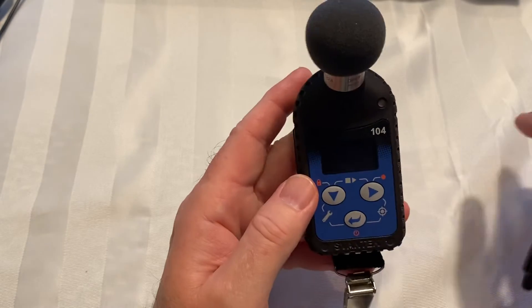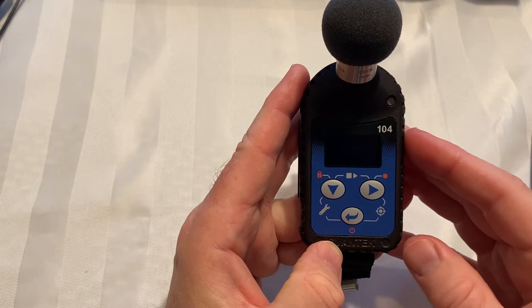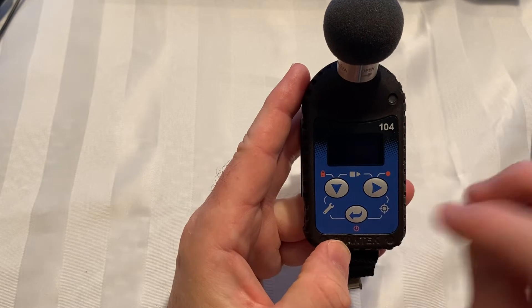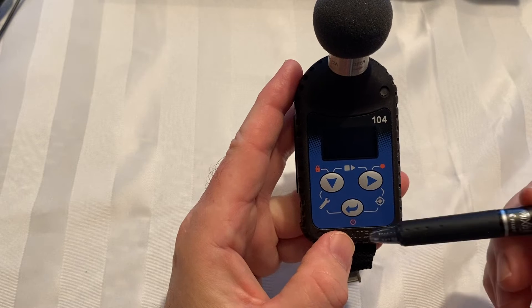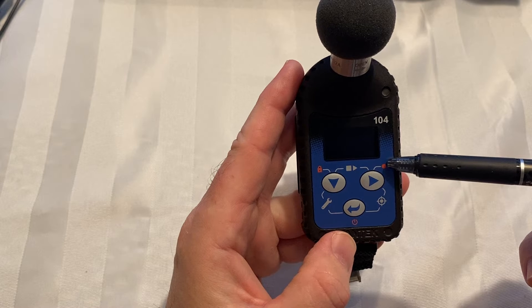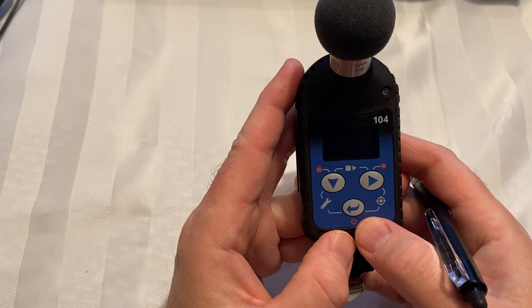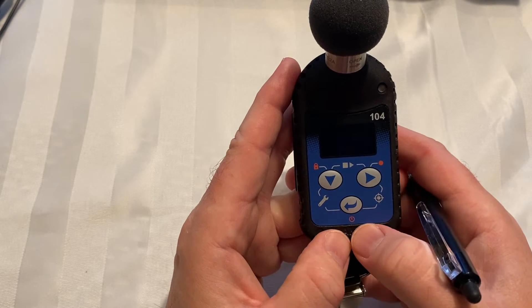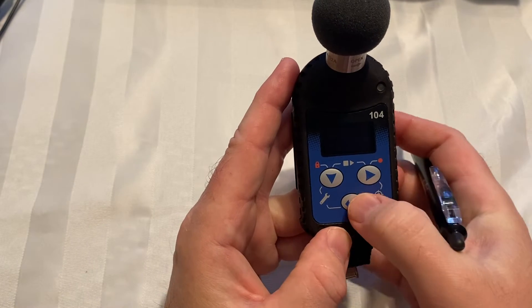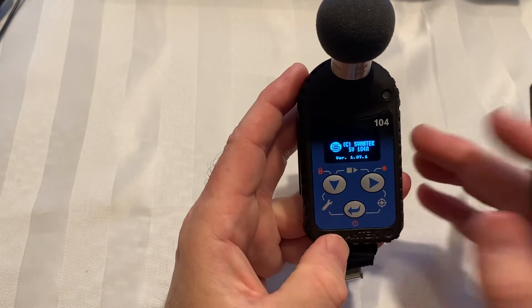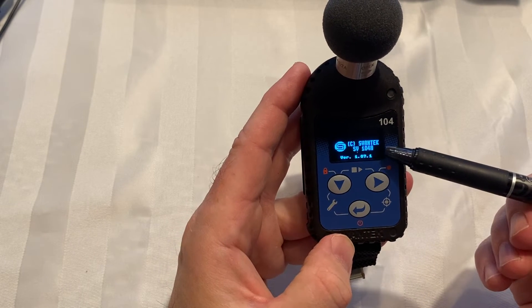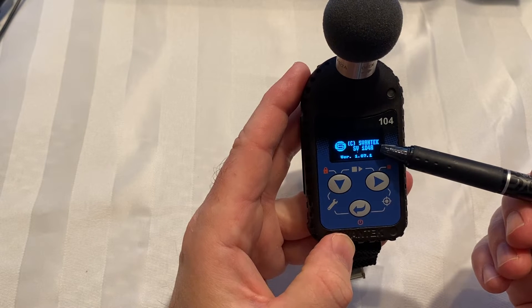So let's get into turning the unit on. Each one of these buttons - this is the enter key - also has a little red indication of the secondary operation. So if I want to turn this on, this is the enter key but it also has a red symbol for on and off. If I hold this down for three seconds, it's going to turn on the dosimeter and it'll go through its boot sequence, showing SV-104A.